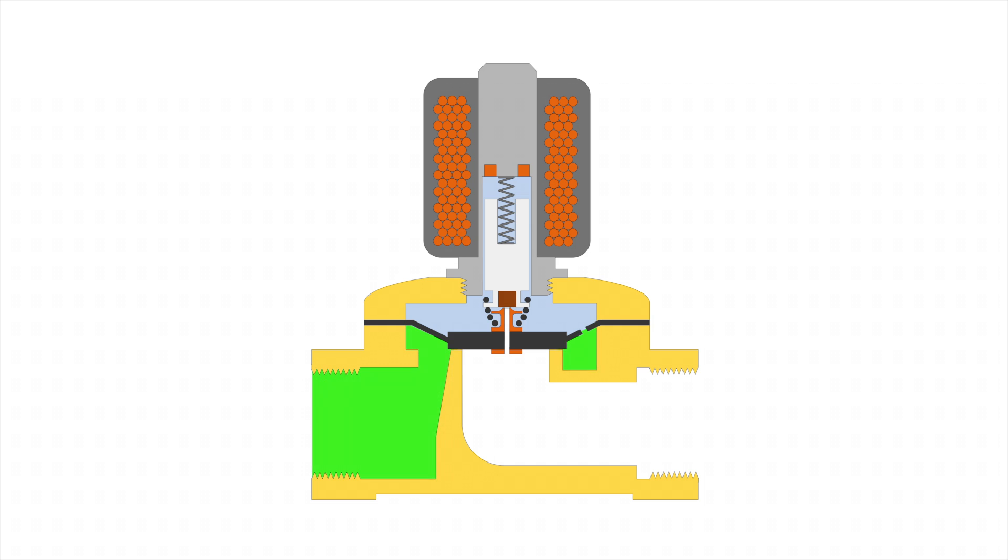In the valve are two chambers that are separated by a flexible membrane. A small hole in the membrane connects the two chambers so that the pressure in both chambers becomes equal. The surface of the membrane in the upper chamber is larger than the surface in the lower chamber. As a result, the membrane is pushed downwards against the valve seat and creates a reliable seal.